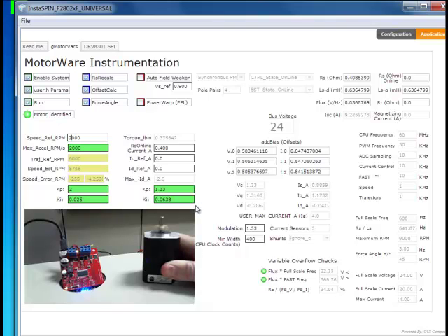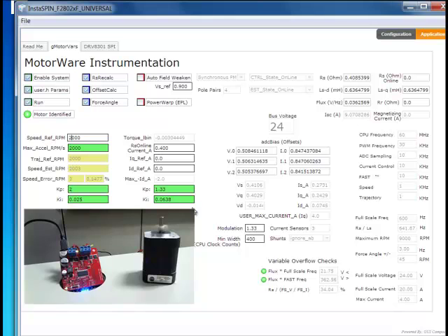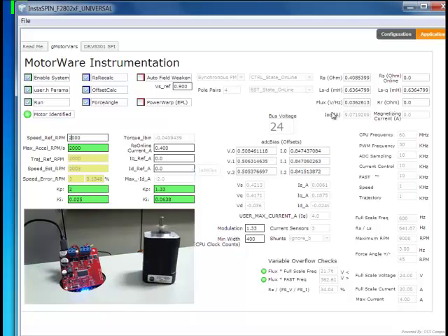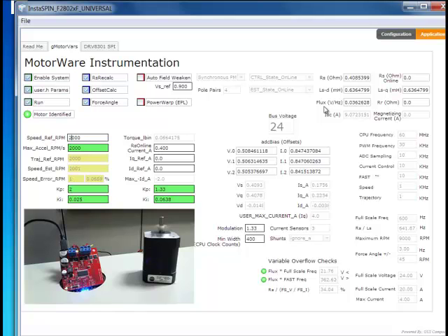Again, I'm going to just reduce the speed here. How we can go faster than even allowing just the maximum voltage is to go into what we call field weakening. This is where we actually inject some current along the D-axis to reduce the effect of the flux or the back EMF that the motor is producing. This can reduce that back EMF voltage and allow us to go to even higher speeds. But it's at a trade-off. You're going to get a reduction in overall torque capability to get higher speeds.